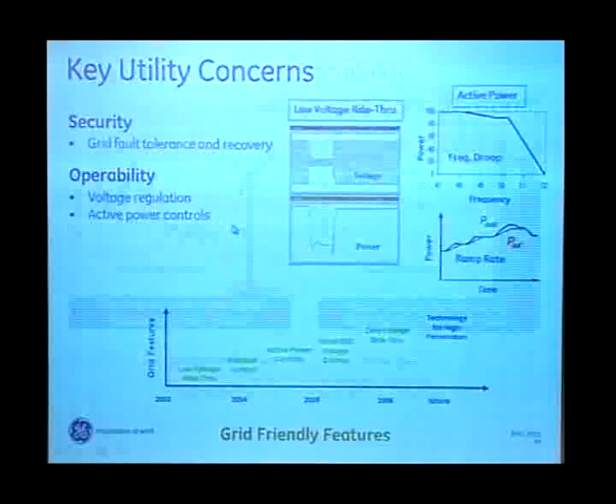Low voltage ride-through was a huge issue in the early days of solar and wind. We wanted the systems to survive a short circuit, a temporary fault, and not go off - that's the primary requirement. This turns out to be a relatively straightforward control feature to add, and these techniques have been developed over the last few years, so I'd put a check mark next to those as things we can do.